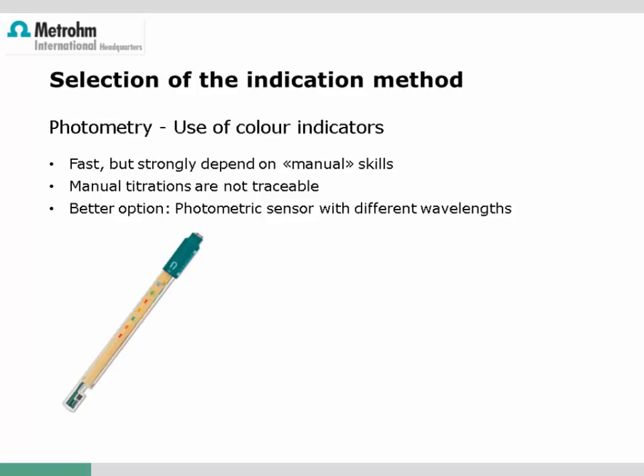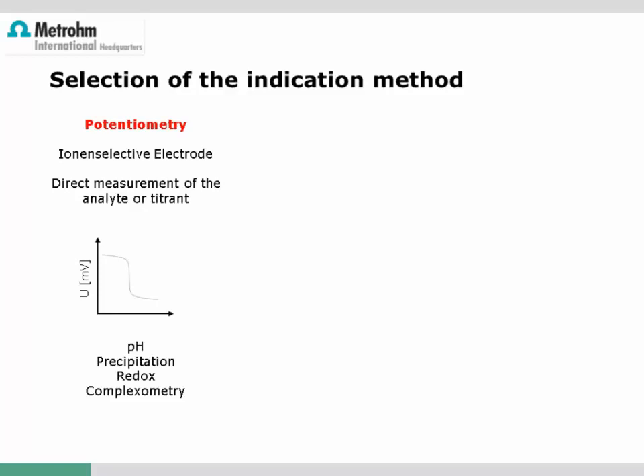Therefore, the better option is to use a photometric sensor like the optrode. Various wavelengths are available in one sensor to cover all kinds of color indicators. The big advantage is that the color change is converted into an electrical signal that can be recorded and evaluated by the titrator — much more reproducible, reliable, and traceable than any manual titration. The only limitation is precipitation during titration, which reduces the measuring signal, so photometric indication is replaced with potentiometric methods whenever possible.